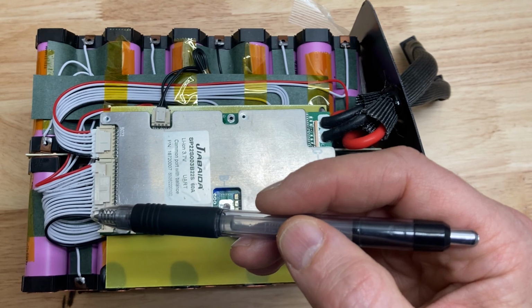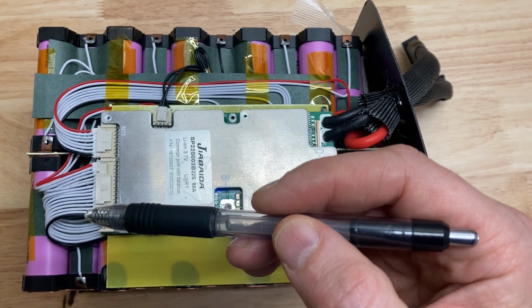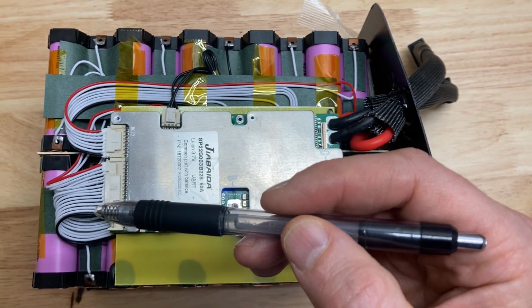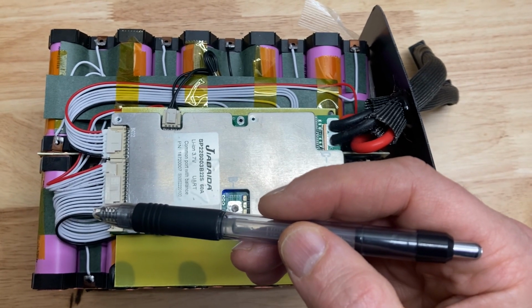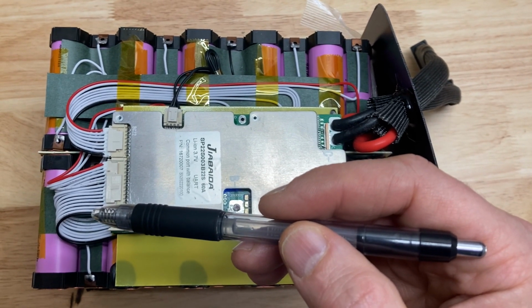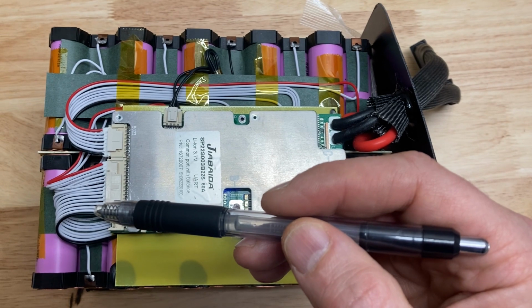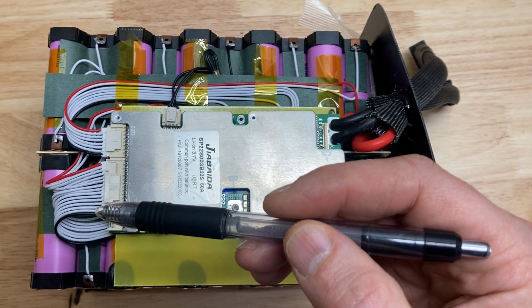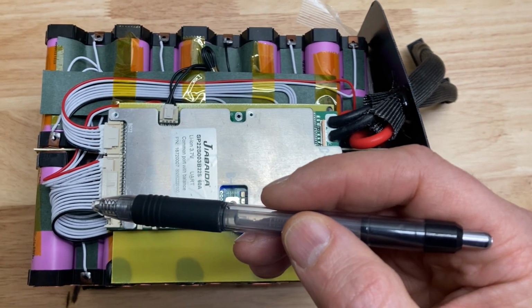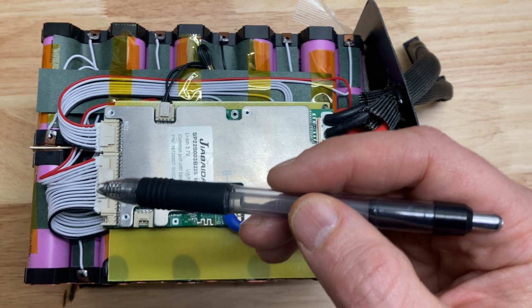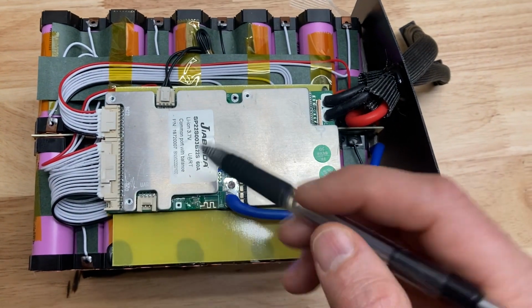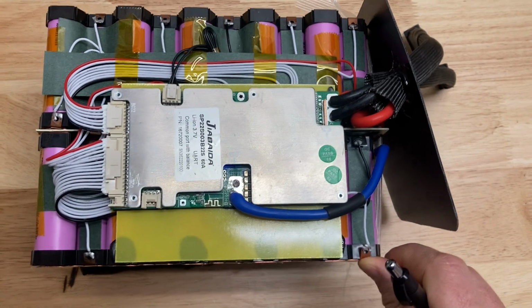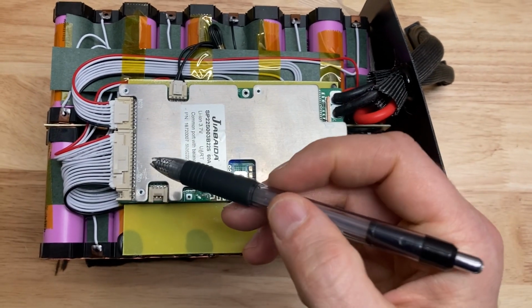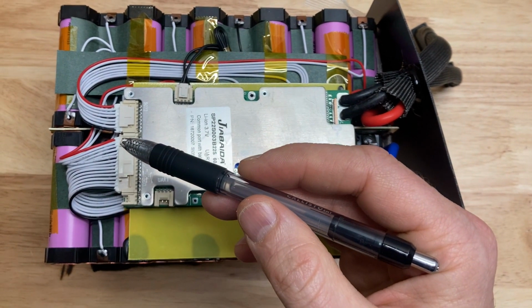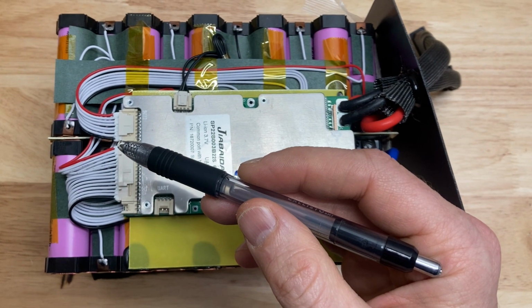When you're wiring this up, you should be able to check it with a voltmeter. This is what JBD and other manufacturers would tell you to do. So if you put your voltmeter on the black wire and the other probe on the first white wire, you'd read 3.6 nominally, then 7.2, then 10.8, and your voltage should walk all the way up until you reach balance lead number 18.